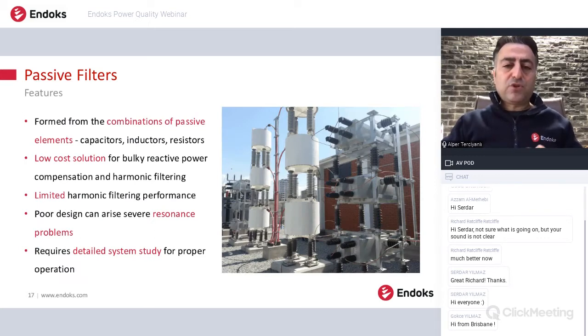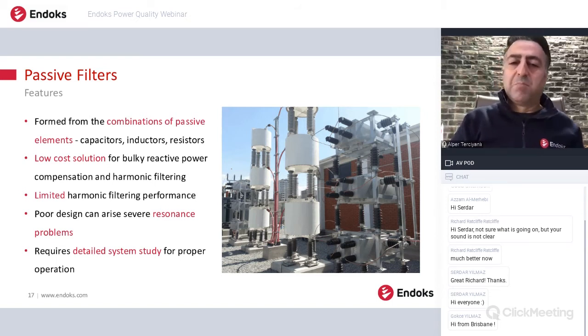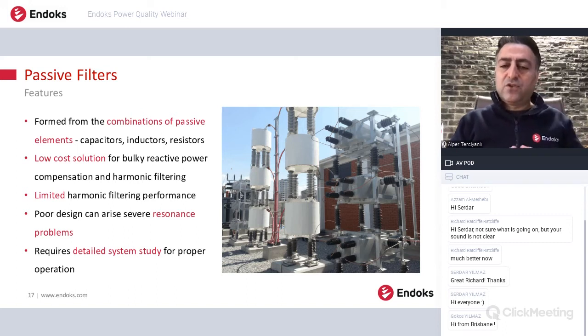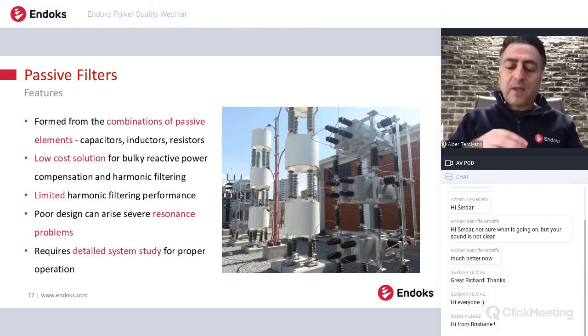And passive filters are the most common solution for eliminating harmonics, because they are formed from combinations of passive elements like capacitors, inductors, and resistors. Since these are passive equipment, it is a low-cost solution. But of course, it is bulky, and since we are using capacitors in these passive harmonic filters, we use them for two purposes: one is reactive power compensation, and the other is eliminating harmonics. We use reactors and capacitors together, and we create filters.